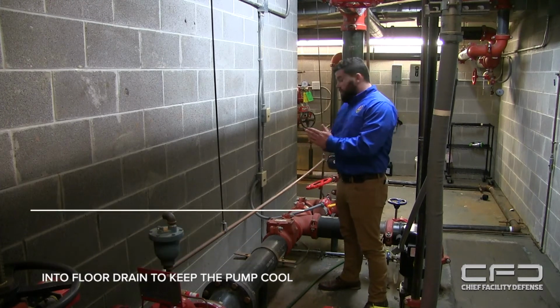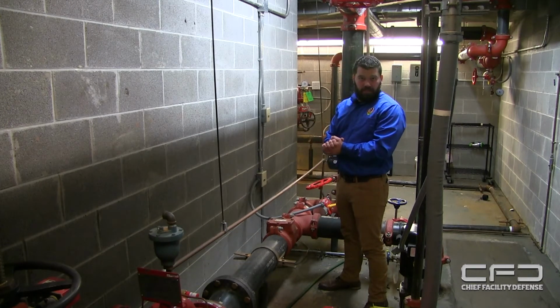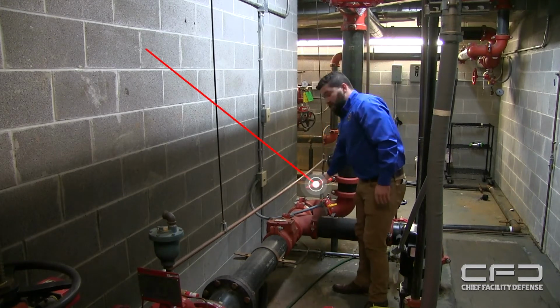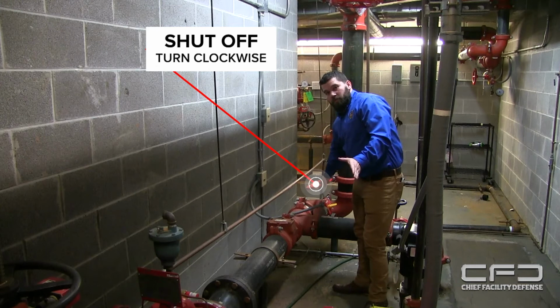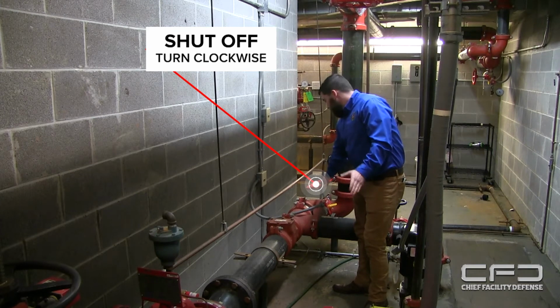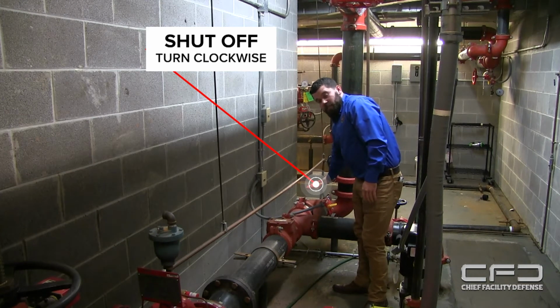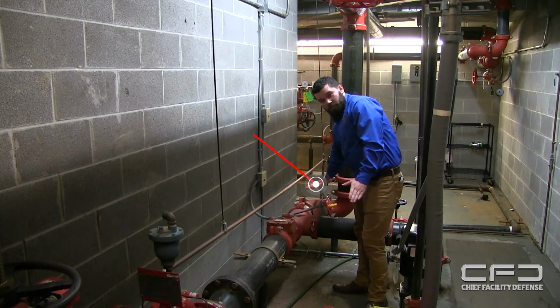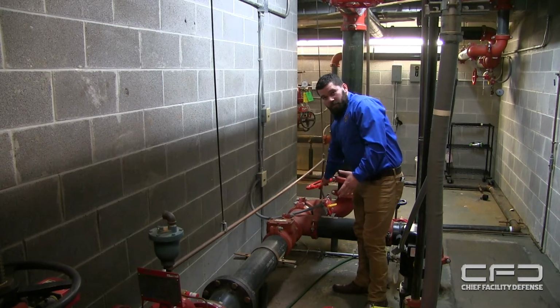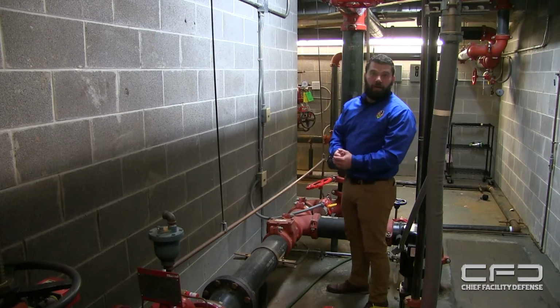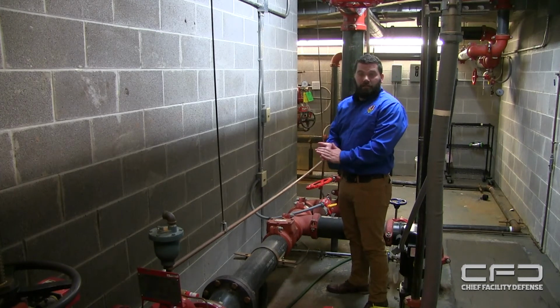And in a situation where there was a damaged sprinkler head, either hit by ladders, vehicles, whatever it may be, this is the shutoff. Again, in a non-emergency situation, you want to turn this valve clockwise. Make sure you do it carefully and slowly. You don't want to cause a water hammer that could damage the pipe, bust a coupling, or create any more damage.